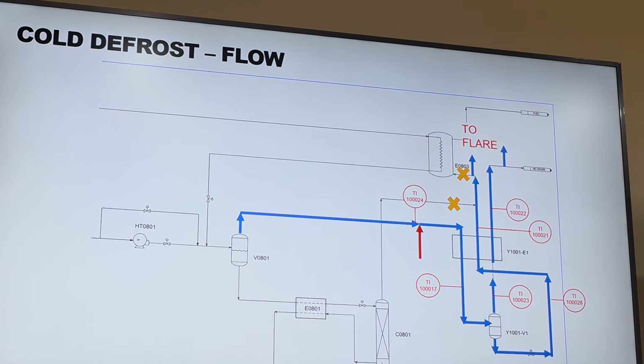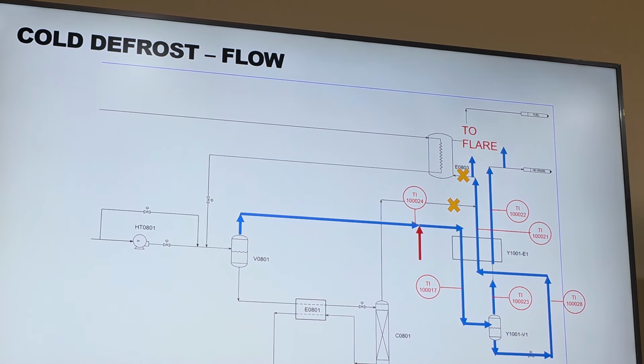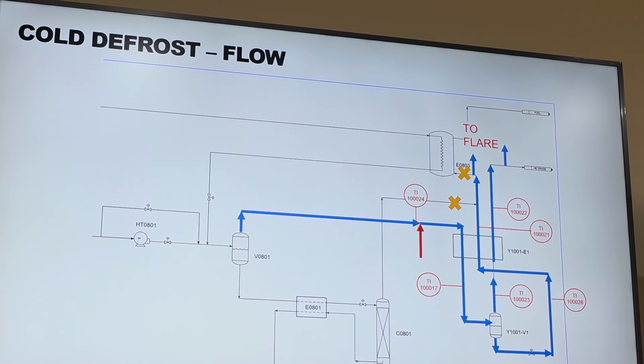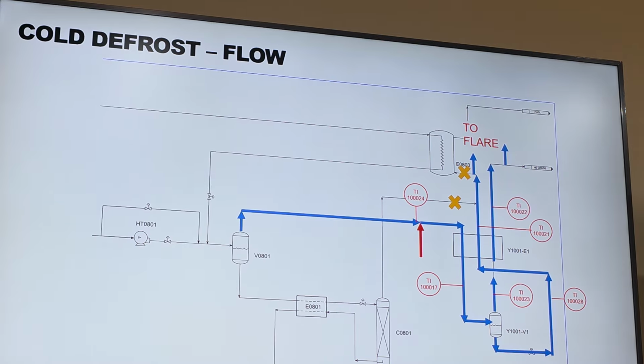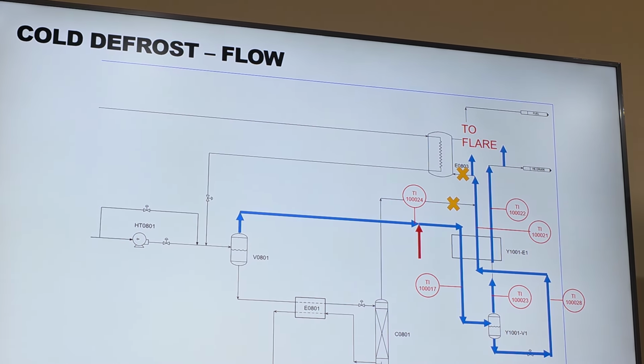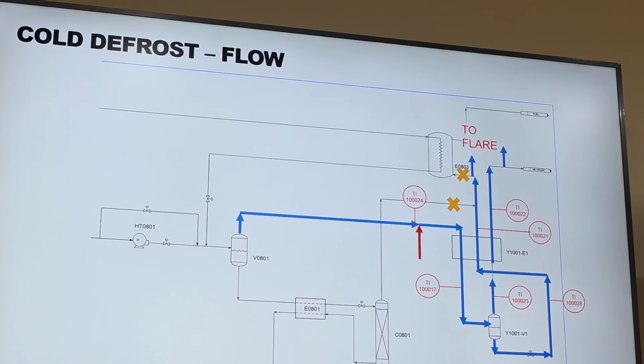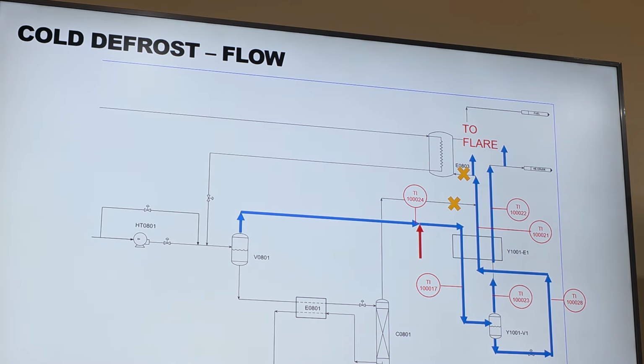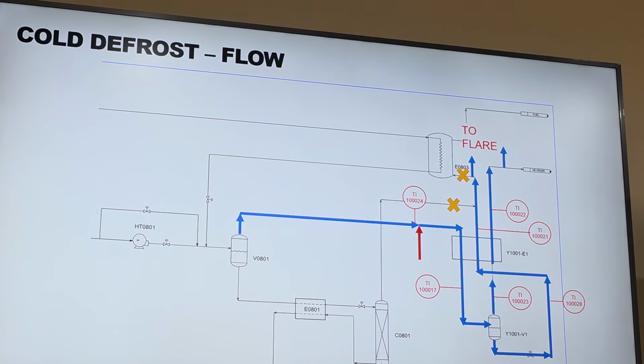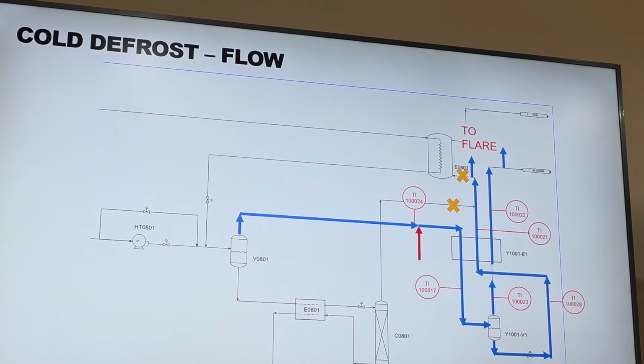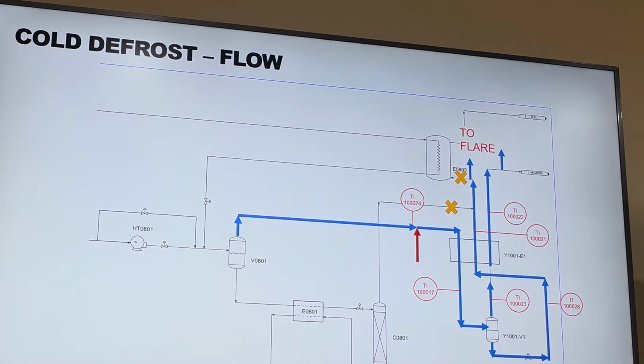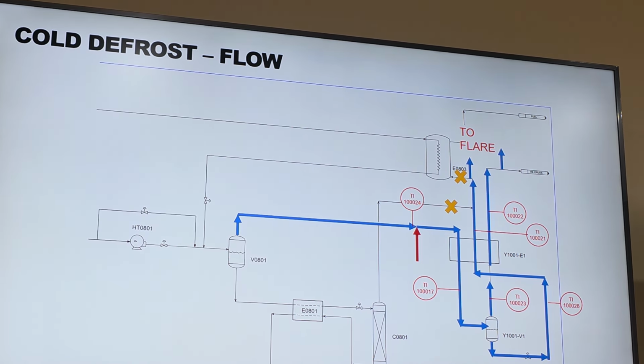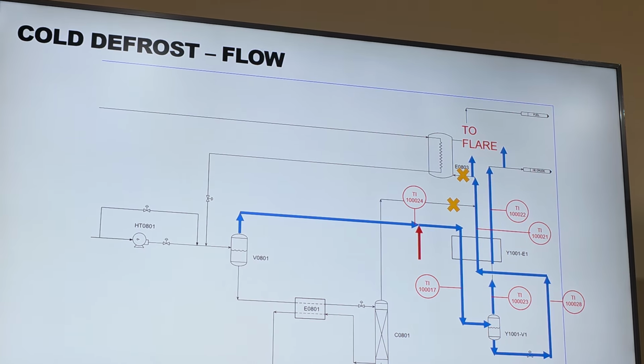How cold can you make your defrost gas when you step it down from 60 bar to 10? If really needed, in such a case as you said, your plant is shutting down and you really need to warm it up. If you are not going to start the train, fine, no problem. You have cold gas available, you can put it into the unit and utilize it. This is one of the options you can utilize.